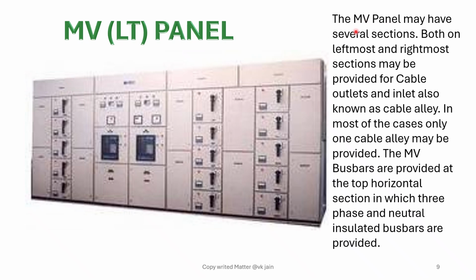The MV panel may have several sections. Both the leftmost and rightmost sections may be provided for cable outlets and inlets, known as cable alley. In most cases, only one cable alley may be provided, but this panel has several cable alleys. The medium voltage bus bars are provided at the top horizontal section.